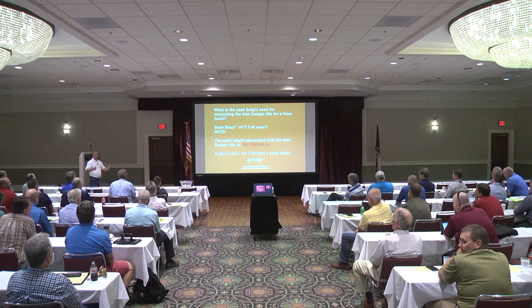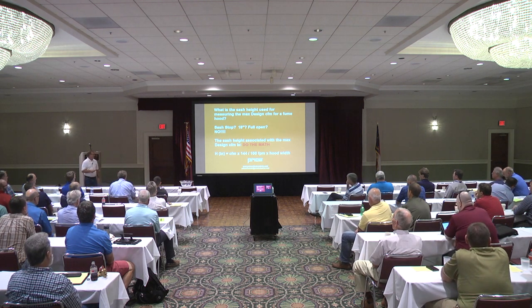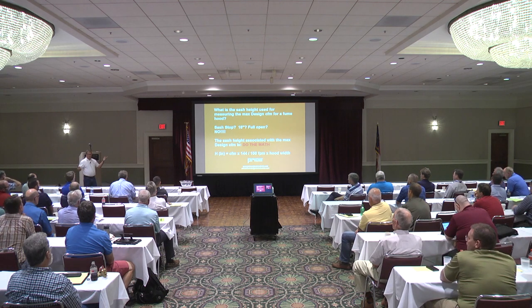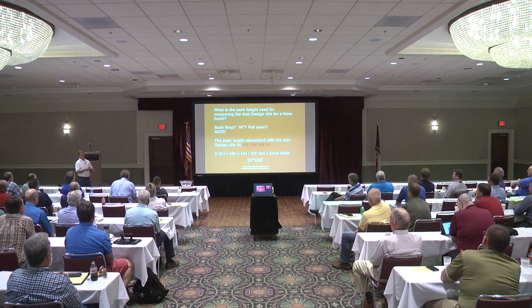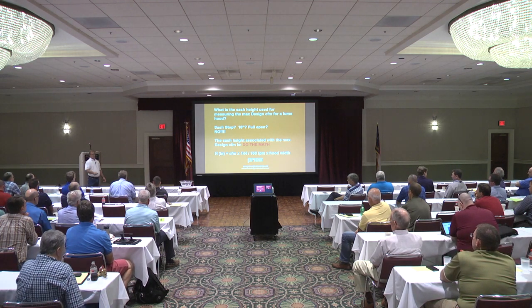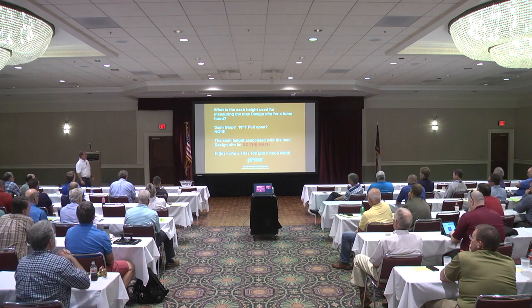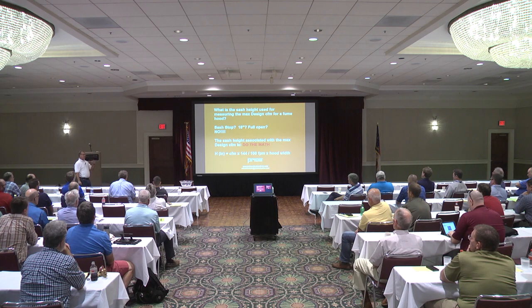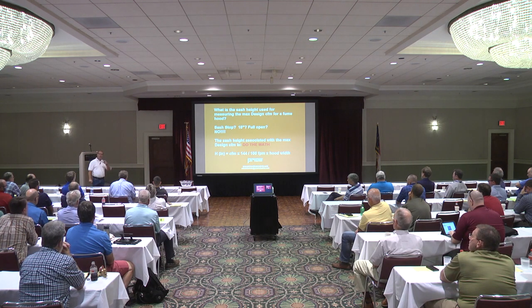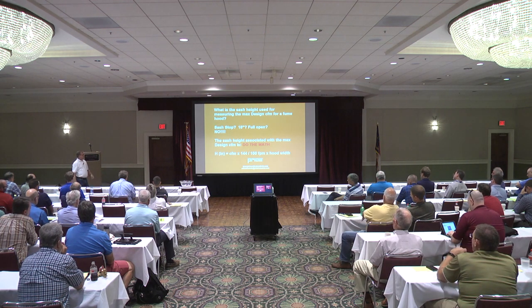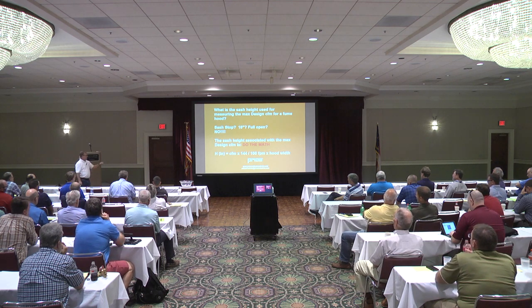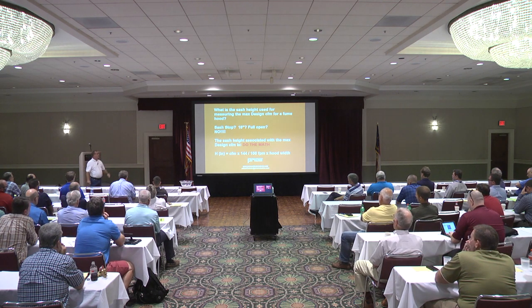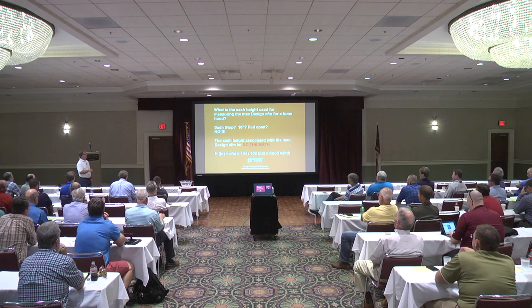Do the math. It's just math. Y'all do math every day in your jobs. You're calculating RPMs, belt sizes, temperature gains. So for the height associated with a fume hood when you're on a new project where you have to test and balance based on the design CFM: CFM times 144 conversion, divided by feet per minute, most fume hoods are 100 feet per minute, times the hood width. That's going to tell you the sash height that hood needs to be tested at.